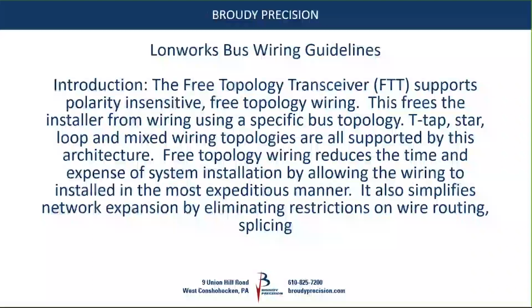The mechanism to communicate with these buses, from our standpoint - Honeywell used LON exclusively for a long time. It didn't switch to using the BACnet product or protocol until around 2010, 2011. So the previous generation of Honeywell LonWorks controllers used a variety of different types of application-specific controllers and freely programmable controllers.